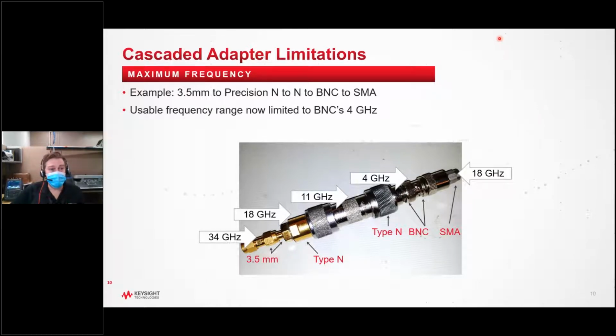You should know what you're doing to your measurement when you do this. It'll work, but how well? When you're cascading all these connectors together, the most obvious issue is you're limited by your lowest performance frequency connector. In this case, it's this BNC, only spec'd to 4 gigahertz. So you could have a 34 gigahertz signal in, and each connector will successively degrade your signal.